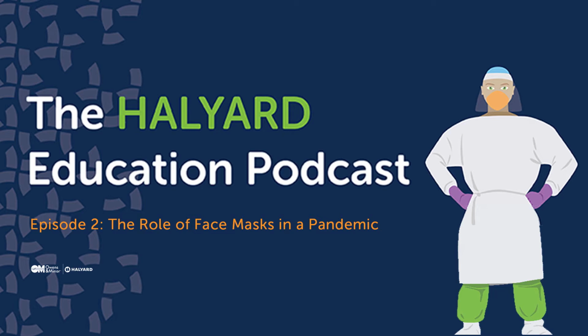What about the flip side, poorly made masks? Are there any visual indicators for masks that likely lack a certain level of quality? So on the flip side, if you have a poorly assembled mask, regardless of the quality or the design, it's going to fail. It can have things like the ear loops could come off in use, or the airflow is going the wrong way. It's going to leak around the edges. And those things can lead to problems. You could get infections, or you put yourself at a risk of infection. If it failed in use, it could fall off. That's going to put your patient at risk. So it's important to have a product that's not just designed to do what you need it to do, but is well made and will stay in use while you're using it.